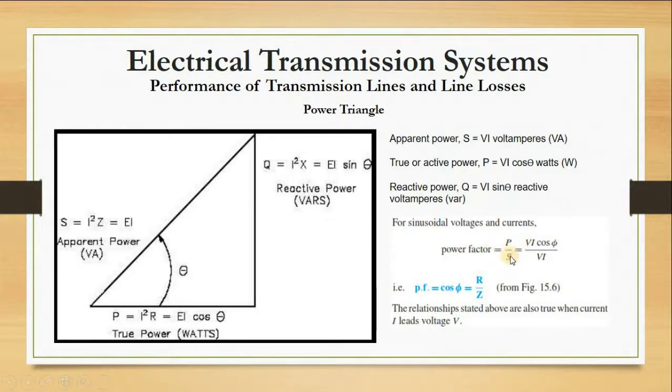But once your power factor begins to drop, as the denominator drops, you realize that now we're talking about S equals P over power factor. As power factor drops, S will have to increase. So the more your power factor drops, the more your apparent power increases and the more your bill. So if you want to reduce your bill, make sure that you target your power factor to try as much as possible to raise it.